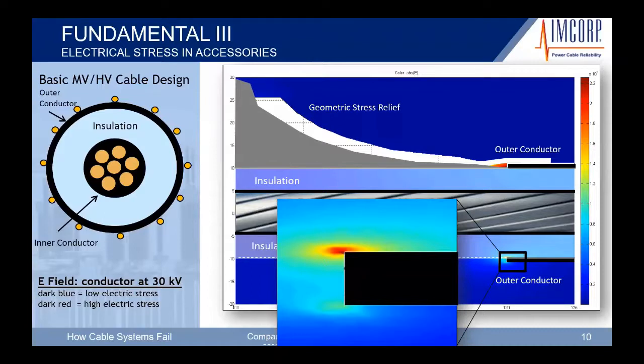That's what we see in most of our heat shrink terminations. Inside of that polymer, that stress control is carbon black. That carbon black creates a unique electrical field, a unique electrical circuit where it's a resistor and a capacitor in series with one another. So these are called pearl chains, and there's a lot of them in there. So you have a voltage drop and a voltage capture, a voltage drop and a voltage capture. And what that does, following the length of the stress control tube, it will eliminate and redistribute that electrical field so that it doesn't damage the cable or the termination.